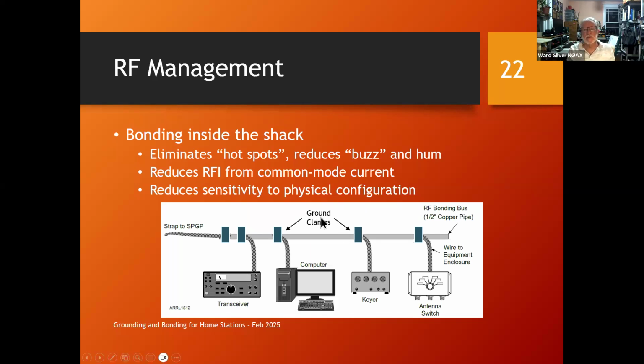What you need to do is use ground clamps. A lot of us used hose clamps - stainless steel hose clamps. But they're not made for metal to metal connections; they're made for holding something flexible like rubber or a hose to something incompressible like metal. If you put a hose clamp on metal to metal and tighten it, come back a day or two later and you'll be surprised how much it's loosened - it will thermal cycle and loosen over time. So use a real ground clamp. A 1/2 inch pipe is just as big as a 1/2 inch ground rod, and that works better. It's more expensive than a hose clamp, but it works better.